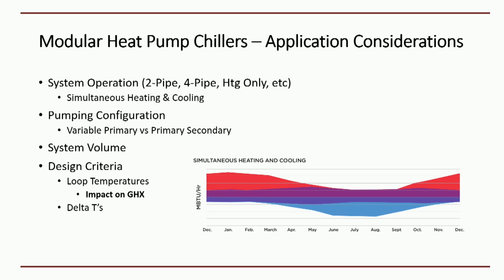I have the same picture, the same graphic Tim used, and that was on purpose, because that is really what we're here for: to get that purple area, that simultaneous heating and cooling. That's what really drives the efficiencies on these systems and gets the best benefit for the owner, and really the team in general. When we're looking at application considerations, though, we always want to make sure that we're paying attention to things like system volume. When we're dealing with refrigeration systems, these are not instantaneous hot water heaters, so we do want to pay attention to that.